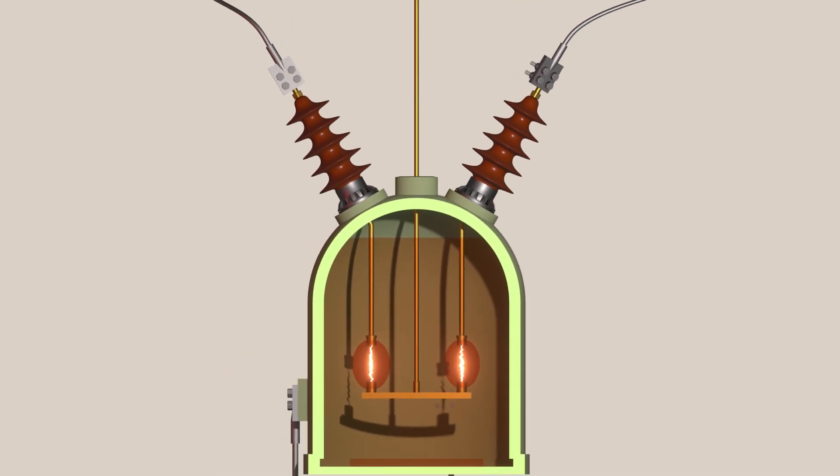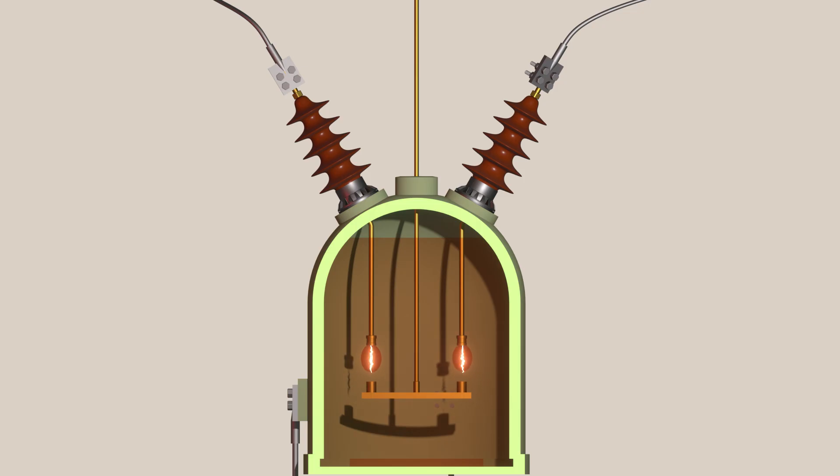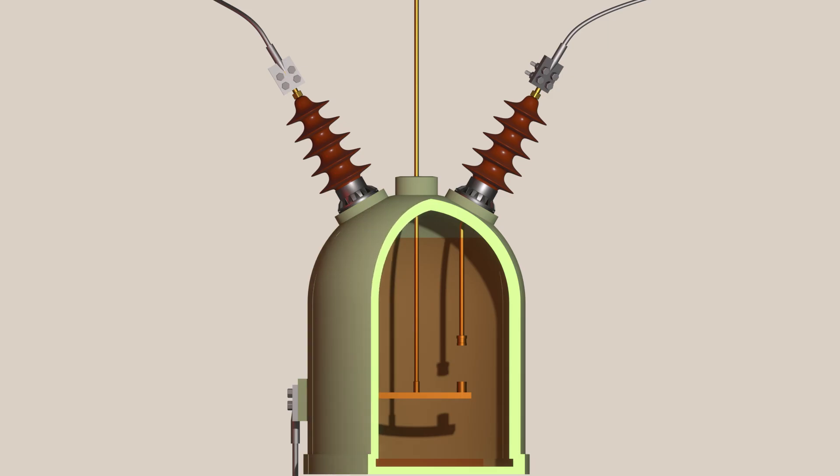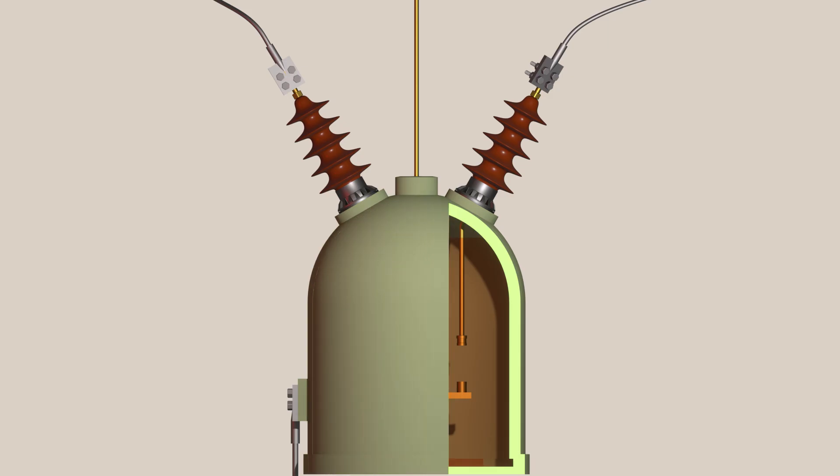After the current passes through zero, the arc naturally extinguishes and cannot reignite immediately. Fresh oil from the surrounding area fills the gap between the contacts, re-establishing dielectric strength. Finally, the arc is quenched. This is how a bulk oil circuit breaker quenches an arc.